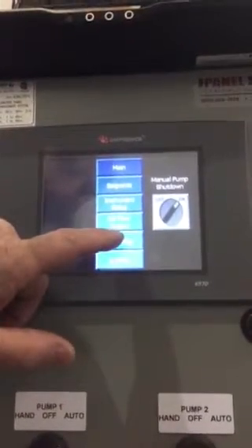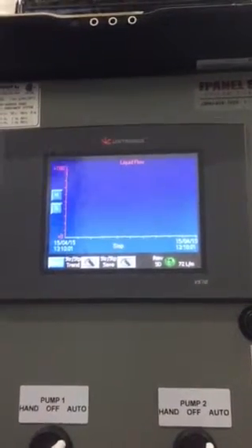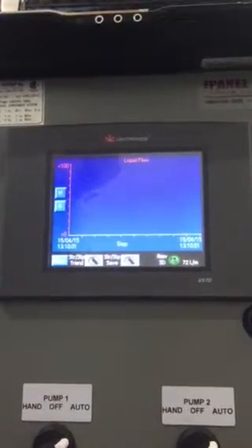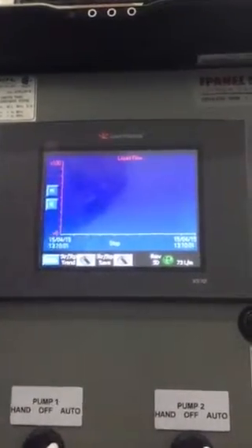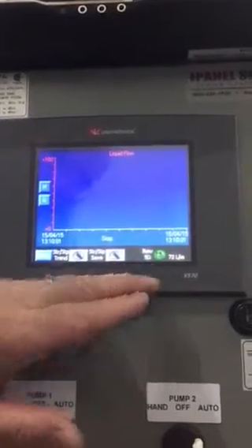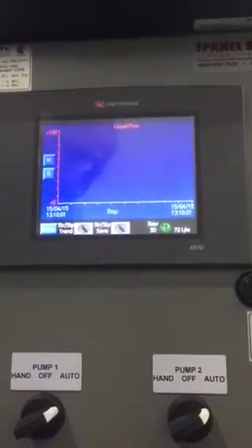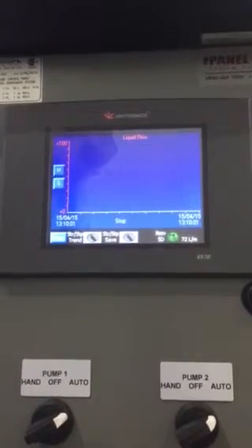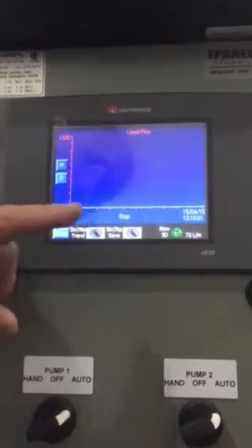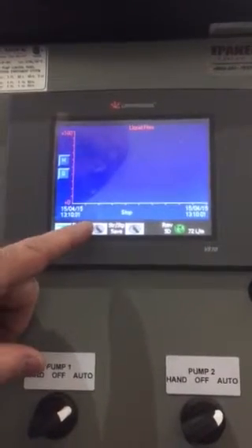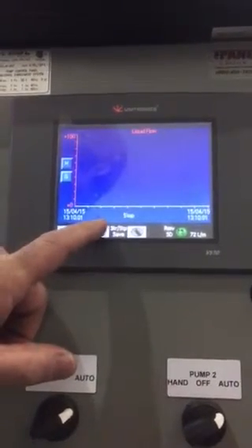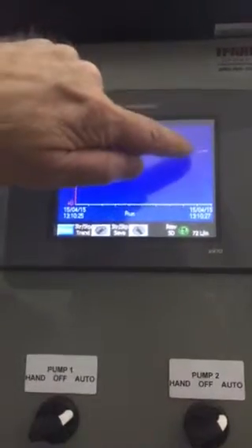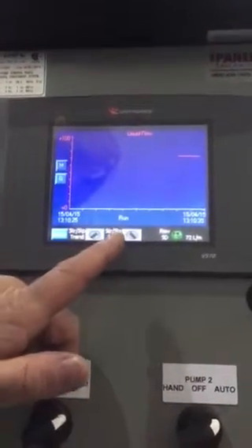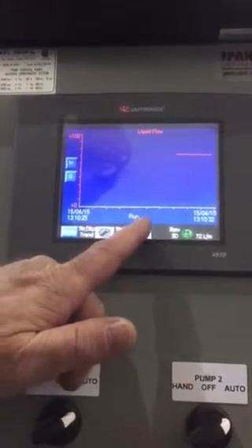So the next thing you have down on the bottom is trending. What this does is it records the amount of flow rate that you have in your system. So you can record it onto an SD card, which is inside of the PLC. It can be removed and put in your computer, or you can download it remotely. The first thing you want to do if you want to start recording to the SD card is Start/Stop Trend. So you hit this first button and it starts to record your flow rate. There's your flow there. If you want to save it to your SD, hit the next button.